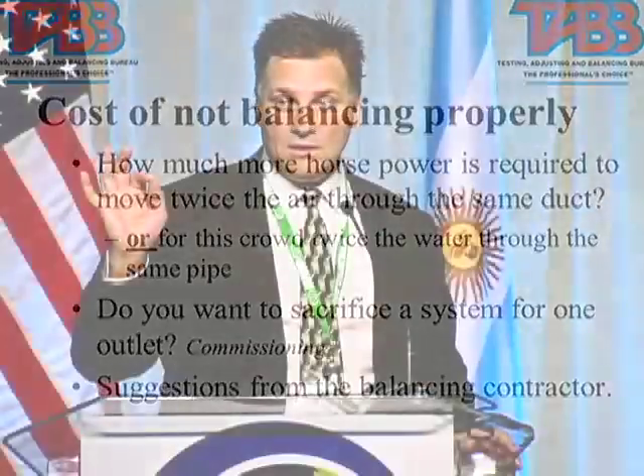Crickets. Eight, exactly right. That is exactly right. It's 8 times the horsepower. So when a commissioning agent says, on that same half-inch pipe that's only delivering half of the flow, as a balancer, you need to make it work, they're really saying throw 8 times the horsepower at that half-inch pipe.